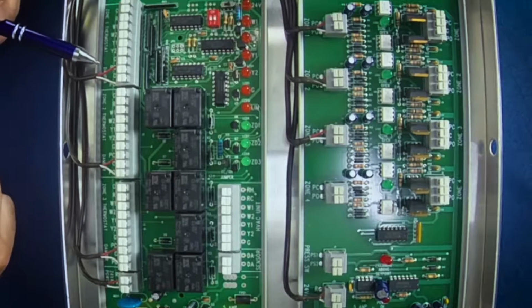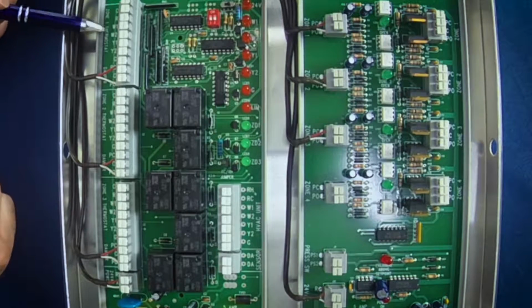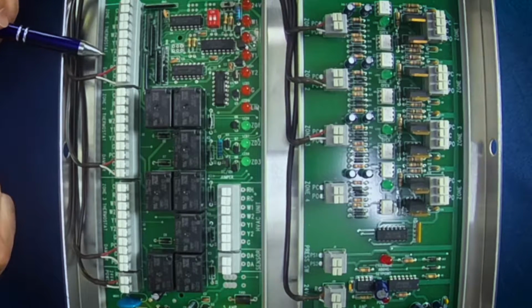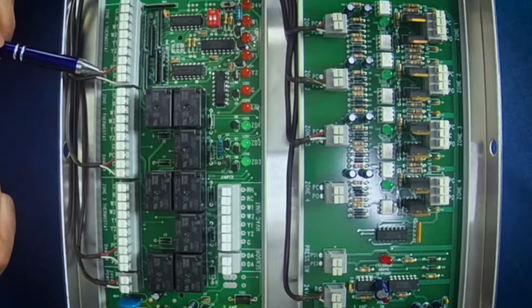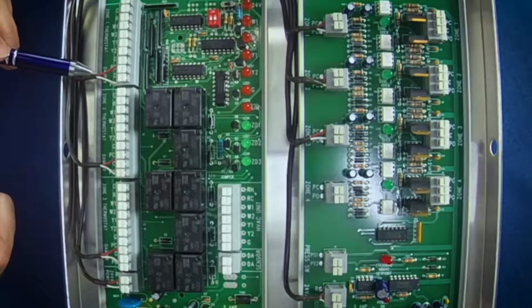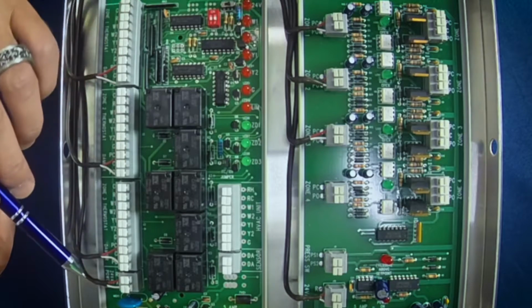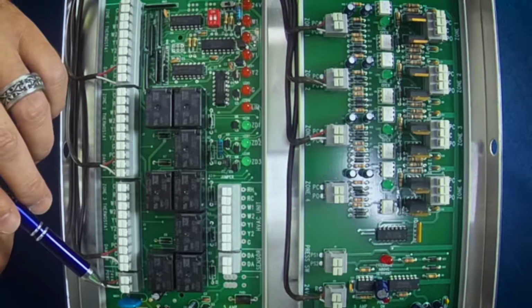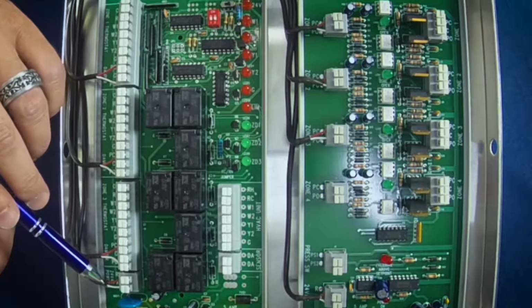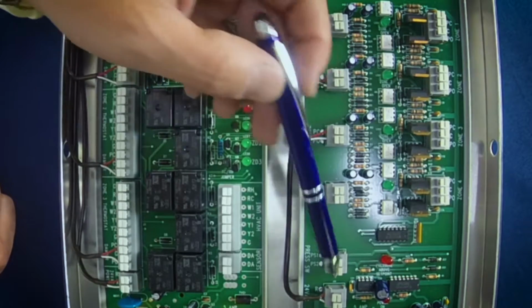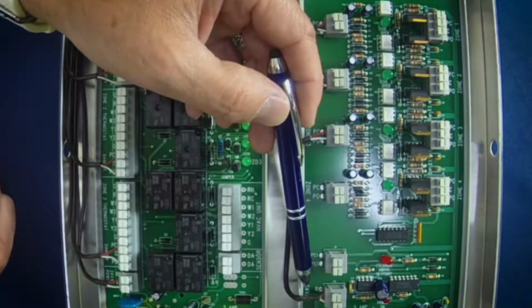So you're going to notice that when it comes down here to the damper, again, this is your thermostat, your hot and your common, your first and second stage heating, first and second stage cooling, and then of course your fan. But you're going to notice that the common wire is not wired in. And the reason why we do that on this is because all we're concerned with is getting power from this panel over to the ESP, and we do that through where the transformer powers in here.